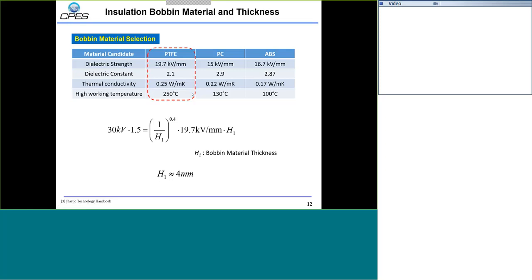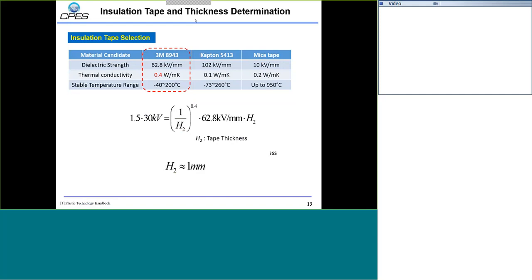We did the same for the insulation tape and narrowed down to three choices. The 3M material has very high dielectric strength and also the highest thermal conductivity compared to other materials. Since this transformer may have larger losses, we prefer higher thermal conductivity for the insulation tape, so we chose the 3M material. With a 50% margin, the total thickness for this tape is 1 millimeter.